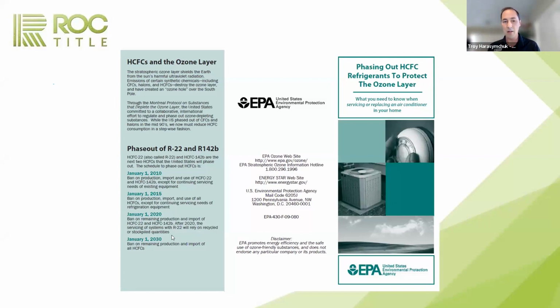So does that mean that R22 is illegal? No. It just means they're not making it, but contractors can still use their stockpiles or have it recycled. And I'll show you an example of that here in a second. So R22 is really not going to be a real problem until January 1st, 2030. So we're still talking 7 years out. By that time, those systems, because they switched over to 410A around 2006, 2007, are going to be so old, they're going to be at their life expectancy anyway. So the government knew that. When they gave us these schedules, they predicted that this would not be as much of a hardship on the general public.